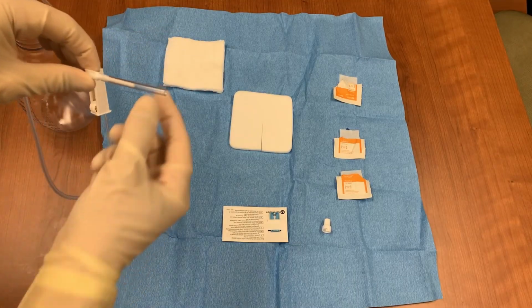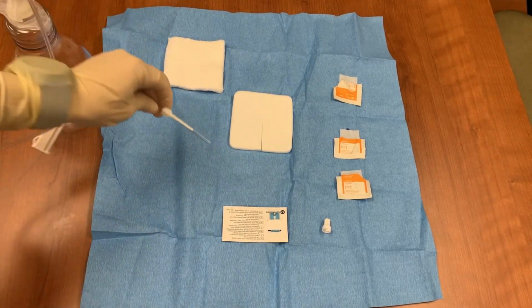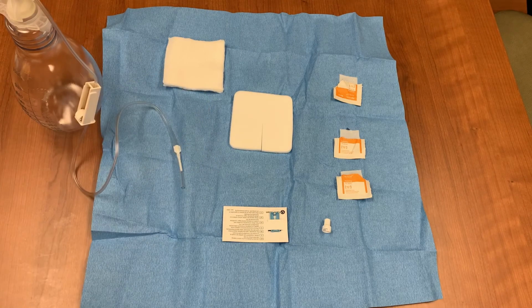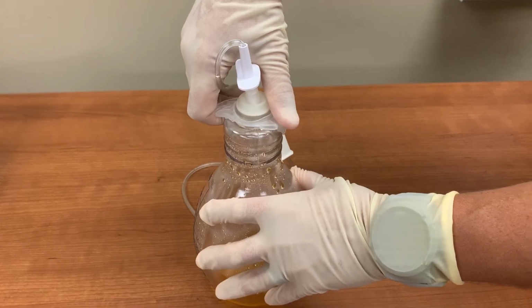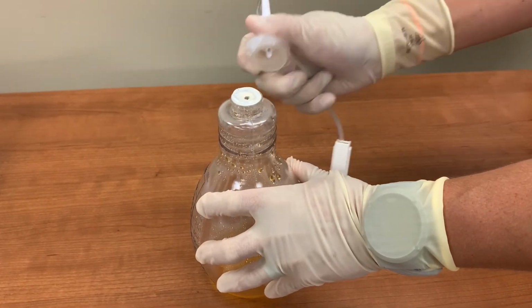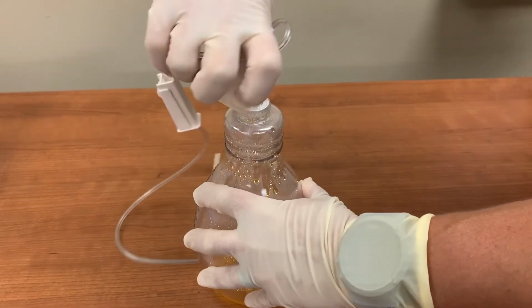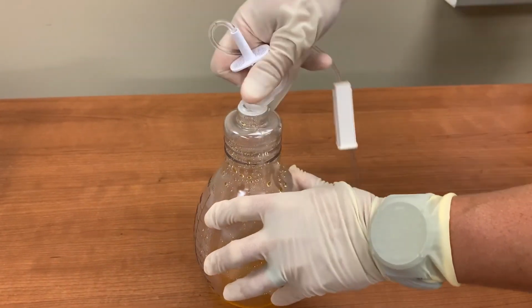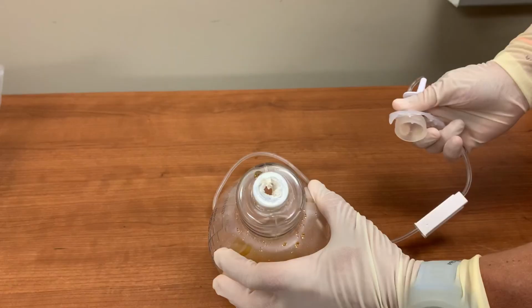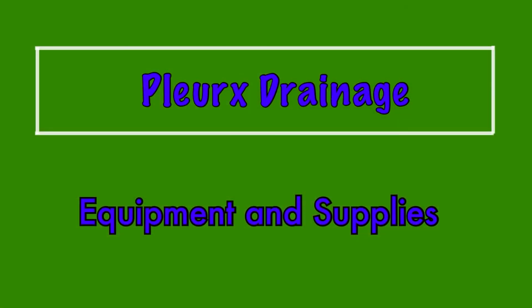At the end of the tubing is the adapter that will fit into the one-way valve of the Pleurx catheter. Care must be taken to ensure that this adapter remains free from contamination, as it will be introduced into the Pleurx system. The final feature of the bottle is the base of the T-plunger. When drainage is complete, it can be removed and used to expand the opening of the bottle to aid in the disposal of the drained fluid. When you have all of these supplies and understand their use, you can begin drainage of the Pleurx system.